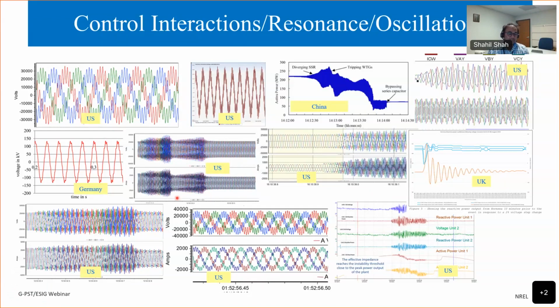So sometimes they are just a nuisance. They don't create any disruptions, but sometimes they are disruptive. For example, in this case, this is a voltage waveform at an offshore HVDC converter in an offshore wind power plant in Germany, and the offshore wind plant started interacting with the offshore HVDC converter, created this resonance, and this high frequency resonance damaged the filter capacitors of the offshore HVDC converter. And that wind power plant, which was rated at 700 megawatt, was out of service just because of this resonance for several months. And if I'm not mistaken, I think it was out of service for almost a year. So you can imagine the economic impact that this kind of oscillations can create.